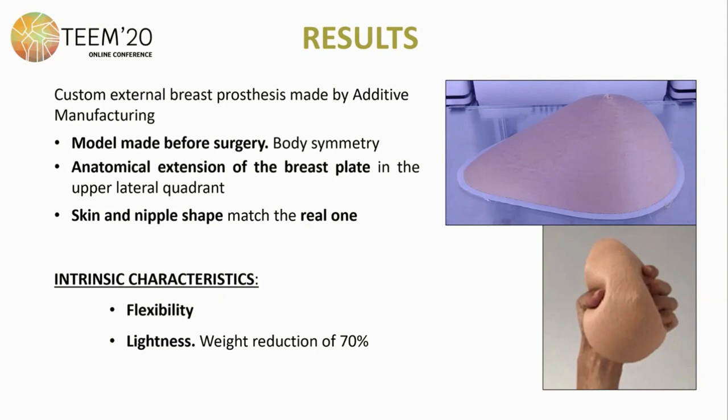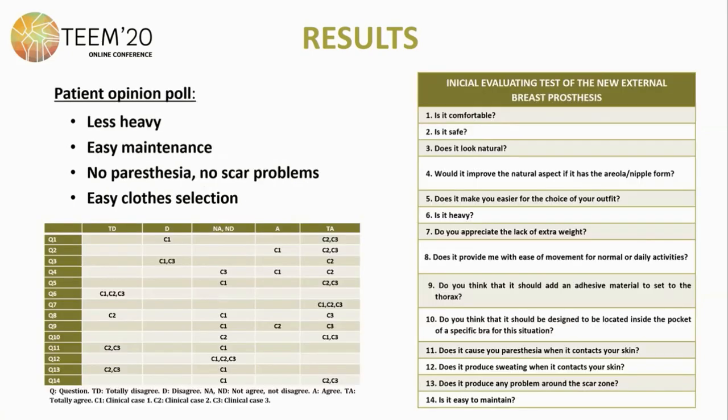As for the results, a personalized external breast prosthesis was made by additive manufacturing. The model was made before surgery to achieve body symmetry, with anatomical prolongation of the breast plate in the upper lateral quadrant. Skin and nipple shape match the real one. The intrinsic characteristics are flexibility comparable to traditional prosthesis models, plus lightness — achieving a weight reduction of 70%. An evaluation poll showed that patients found it less heavy, easy to maintain, with no paresthesia or scar problems, and easier clothes selection.